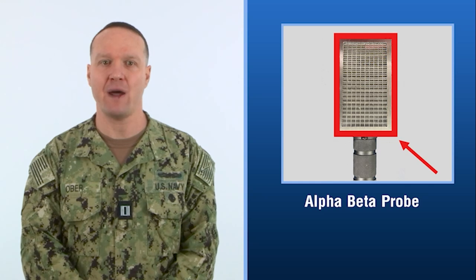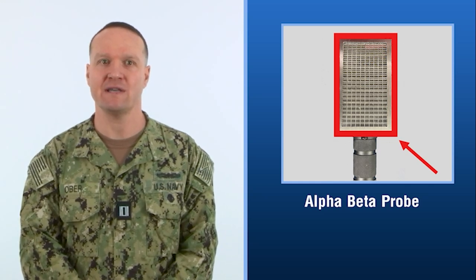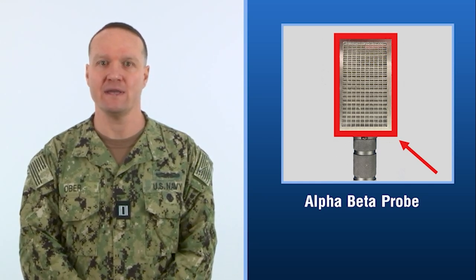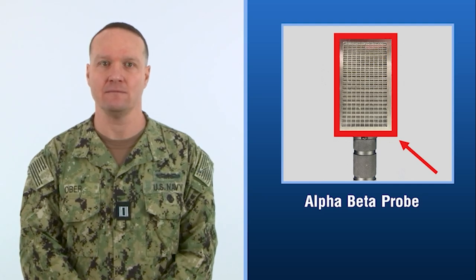Lastly, it is important to ensure that the detector inside the probe is not exposed to ambient light. And again, the mylar window, which covers the detectors in the alpha-beta probe, is designed to block ambient light.